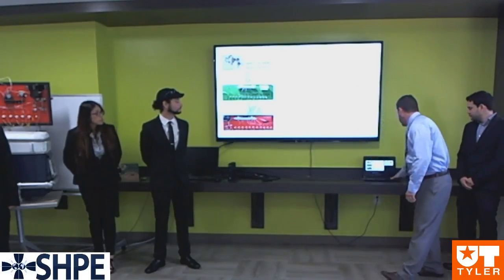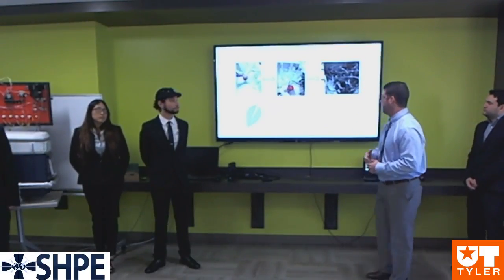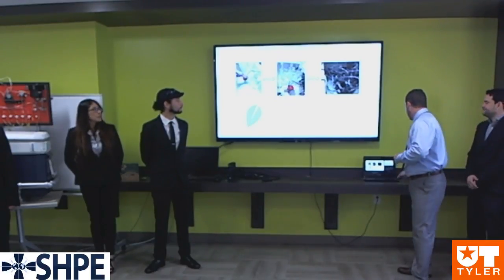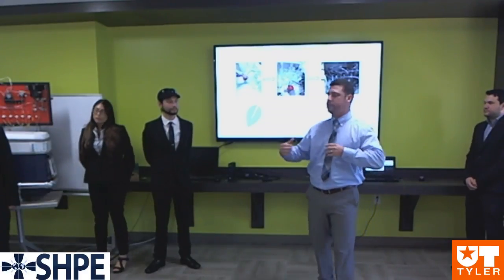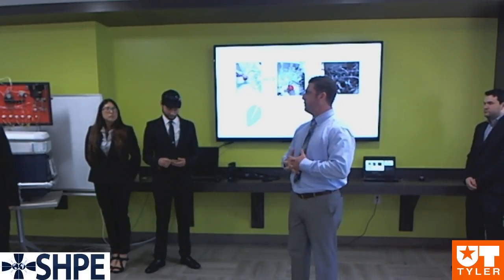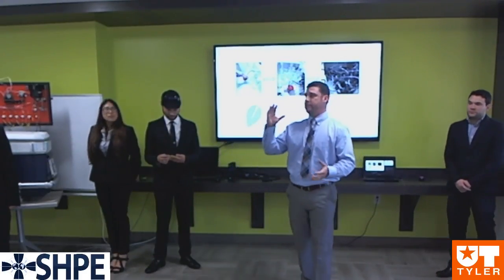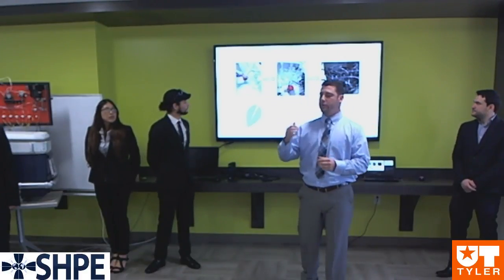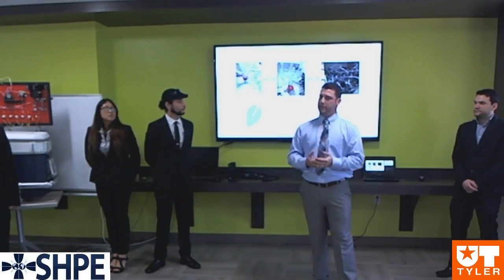I'm not going to talk much about the heating unit because that was pretty much a success from the beginning. As far as where you saw the graph, we successfully long-term were able to heat the water. But a really good example of how, when we integrated these systems and took them from individual components to working as a whole, we overcame some challenges is that the condensing units that we calculated that we would need were massive. The one that the other university in Texas used were huge. They're very expensive. They're going to cost over $200, $250 a piece, and we needed 12 of them. It's not feasible for our project.